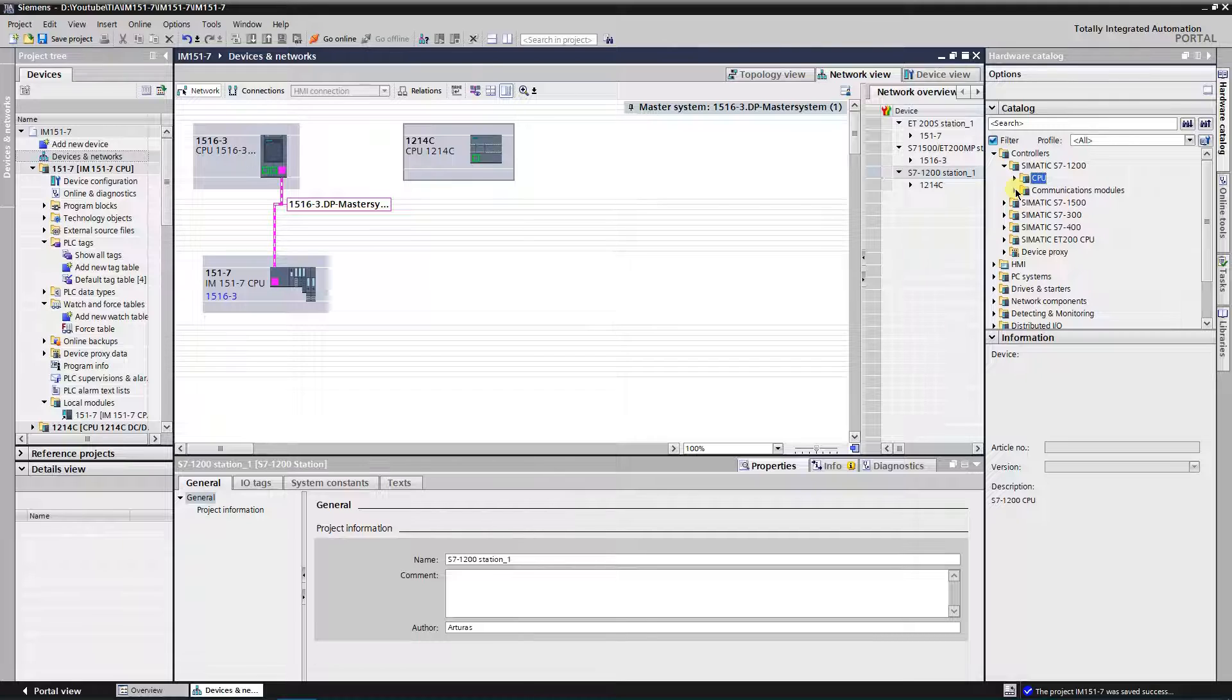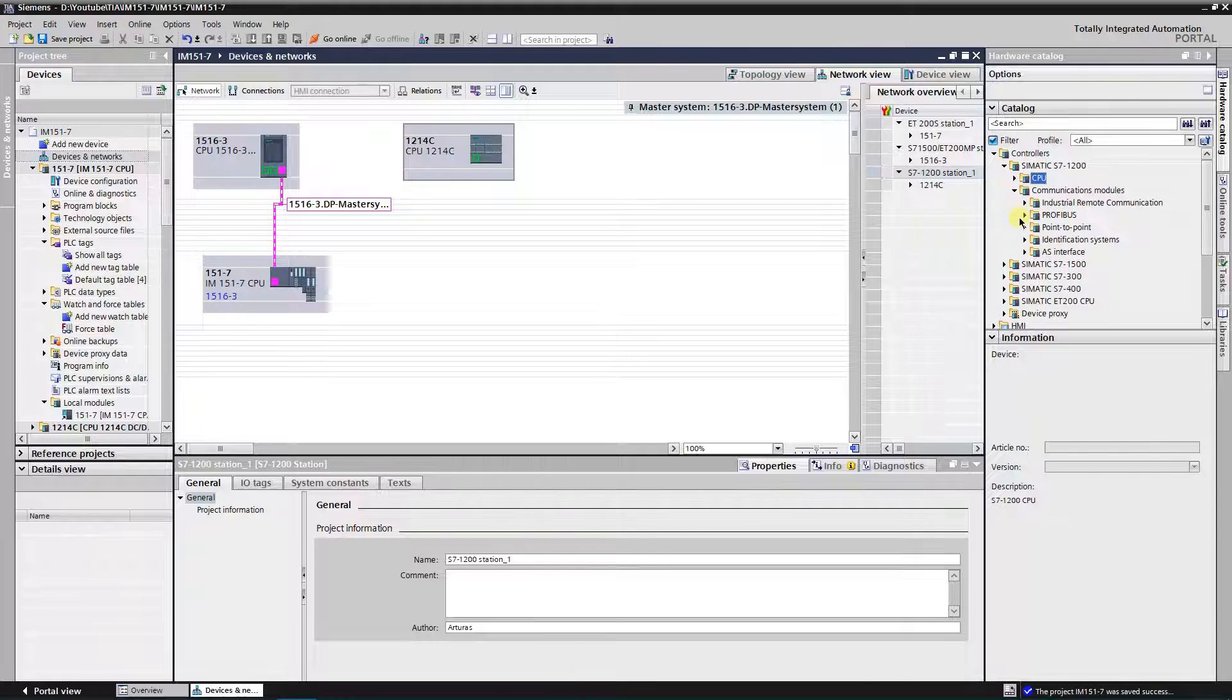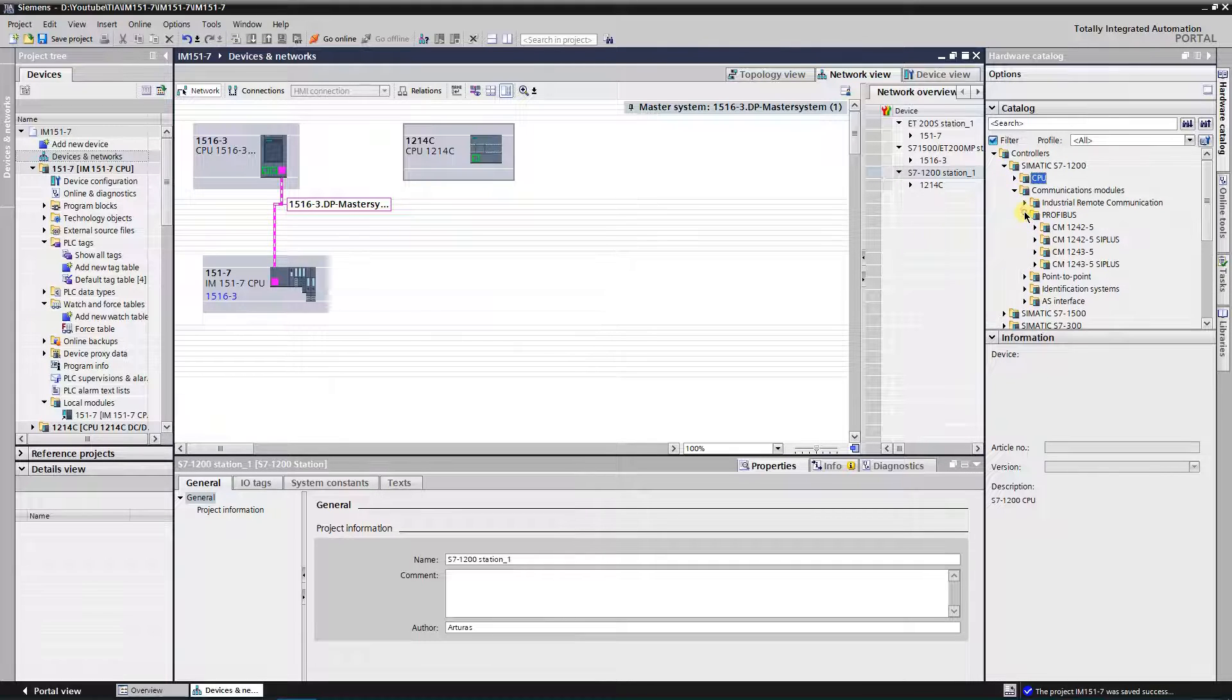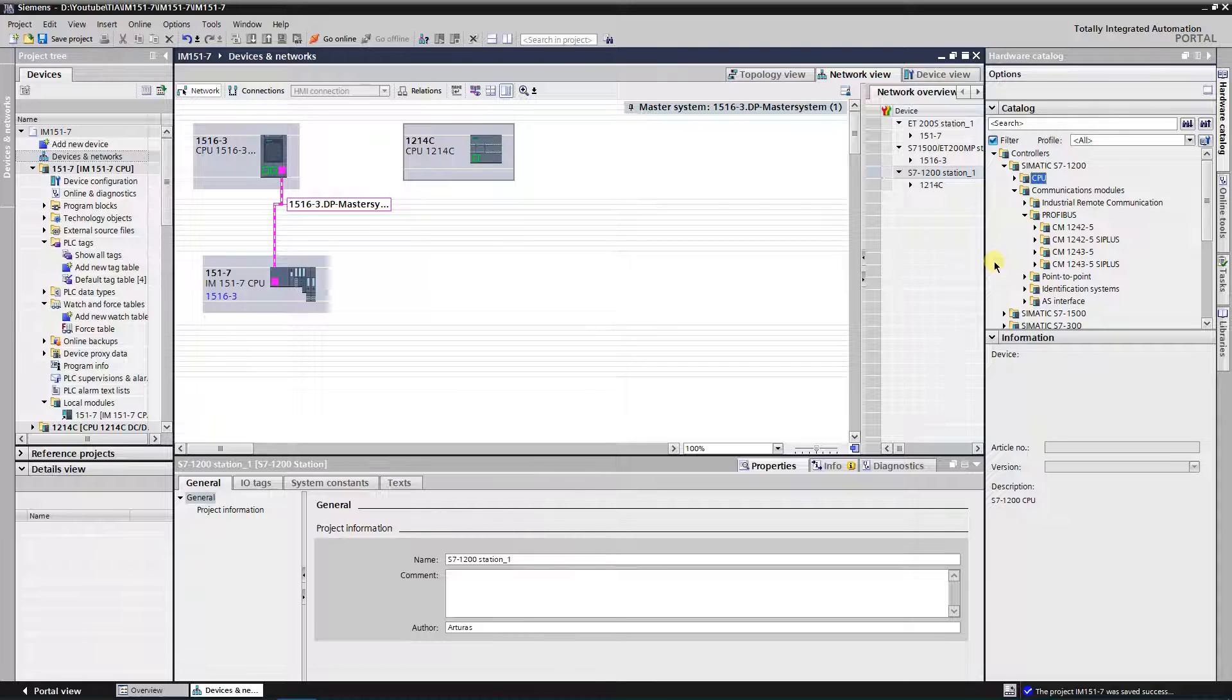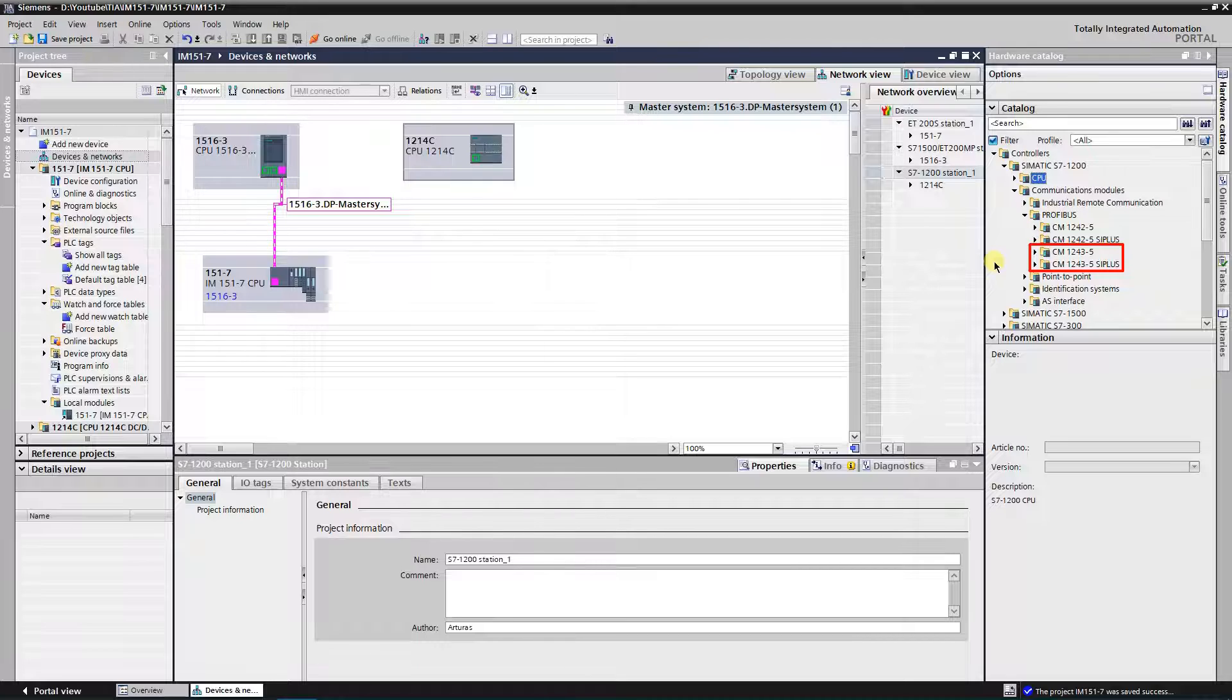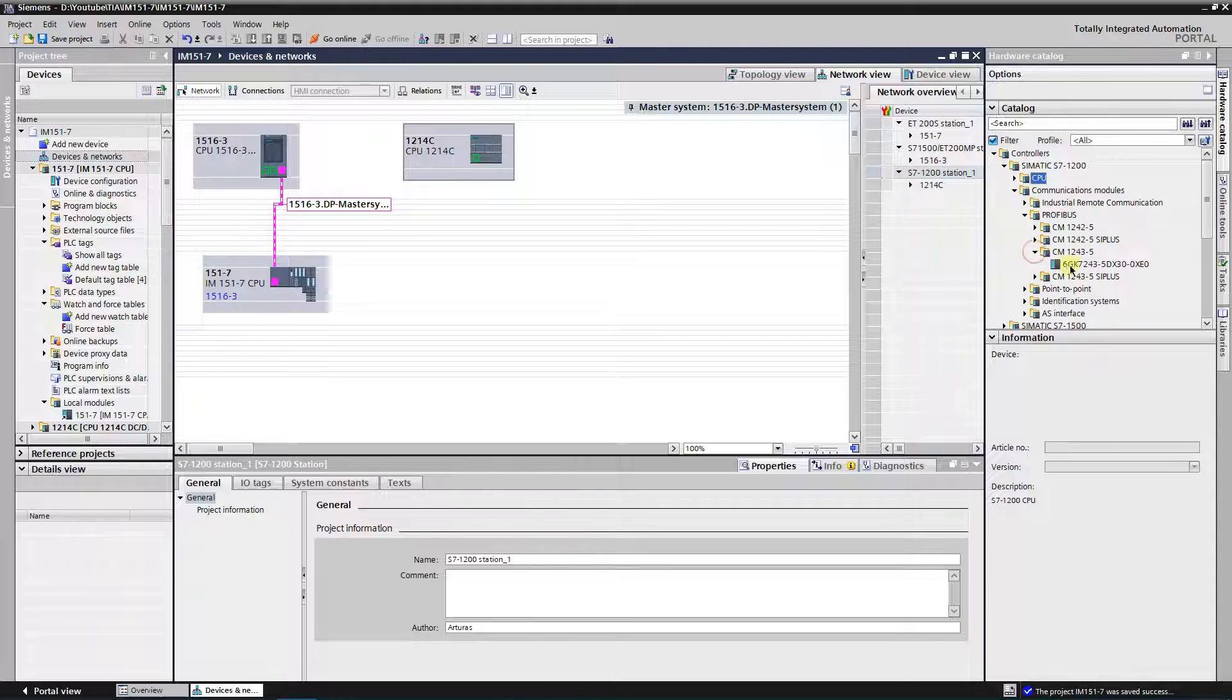Find the folder named communication modules in the SIMATIC S7 1200, under the controllers and expand it. There are two communication modules, one is CM 1242-5, it is used to connect S7 1200 to Profibus DP as DP slave. Another one is CM 1243-5. It is used to connect S7 1200 to Profibus DP as DP master. This module is needed for our application. Insert it into the S7 1200 system.